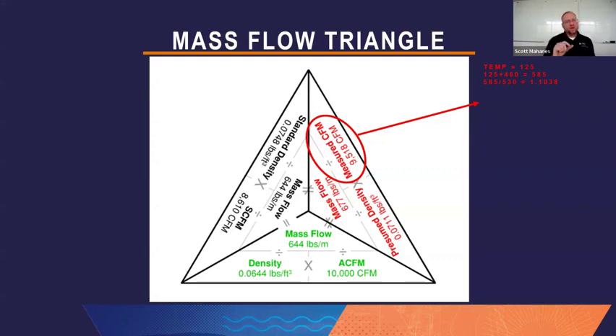And so if I have a 125 degree temperature, I need to turn it into an absolute value of 585. Divide it by the standard absolute of 530 and get a factor of 1.1038. When I have that factor, I need to take the square root of it in order to get a correction factor for the velocity or volume. And so this is really nothing new. This is by the book of correcting for temperature from my measured value that doesn't correct for temperature. It's considering 70 degrees standard temperature. And so what's interesting about this case is I've accurately measured 10,000 CFM now.